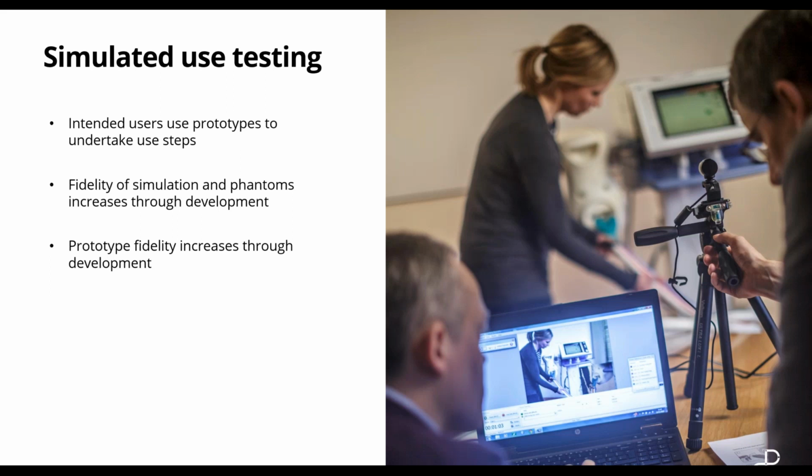So for something like a surgical product, it may be beneficial to do that user testing using a highly realistic phantom. However, in the early stage of development, that may not be possible, and there might be more low cost and simple ways of creating a simulated use environment when you have a lower fidelity model.